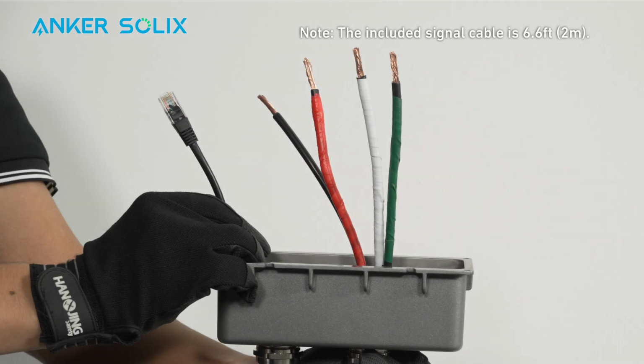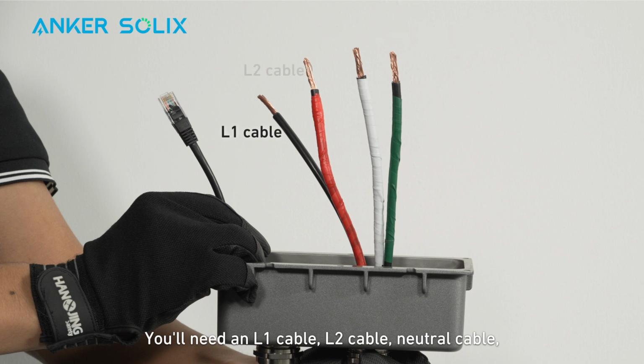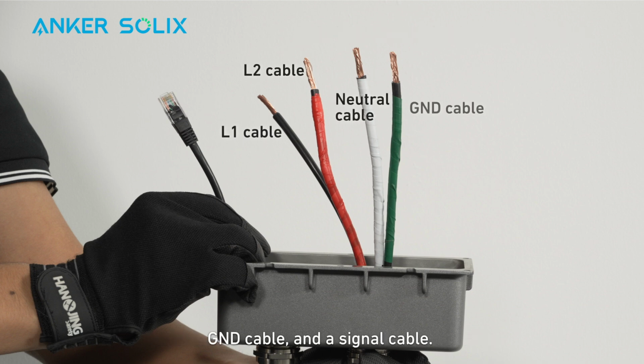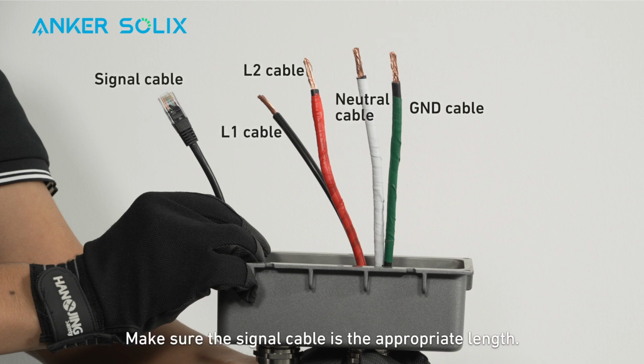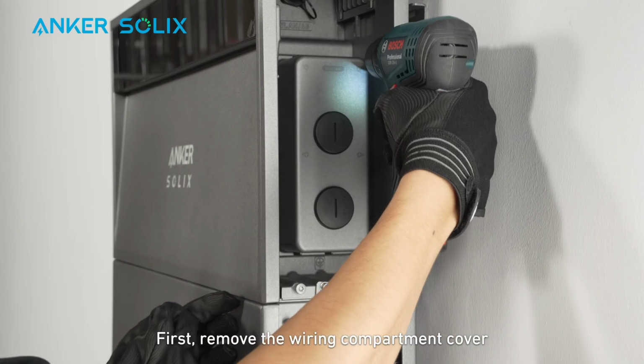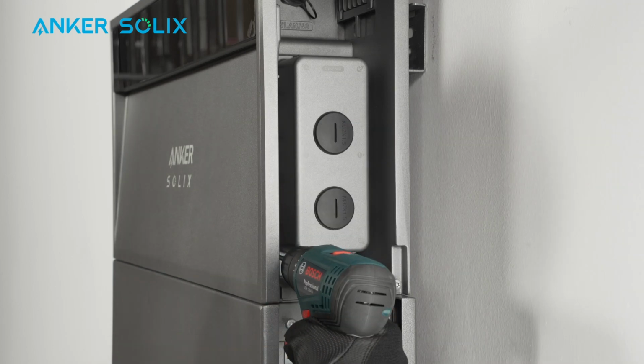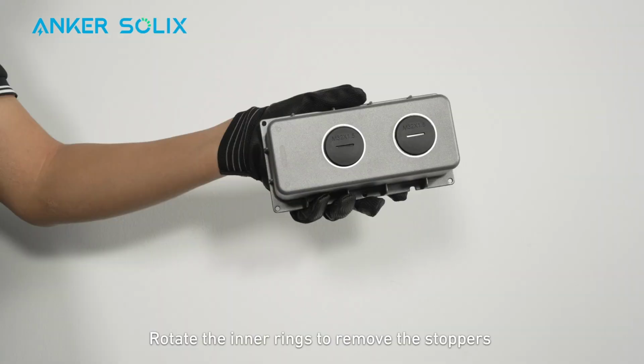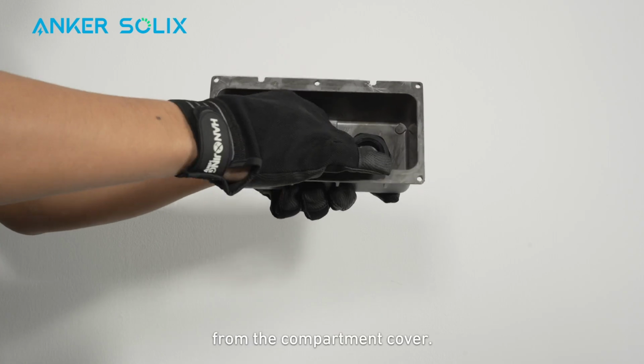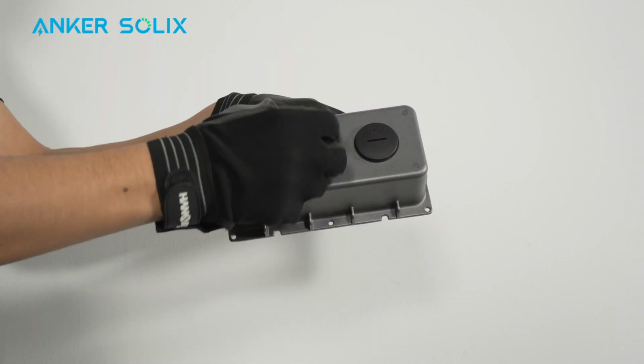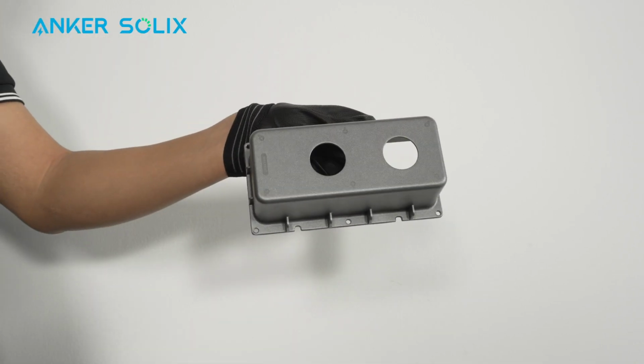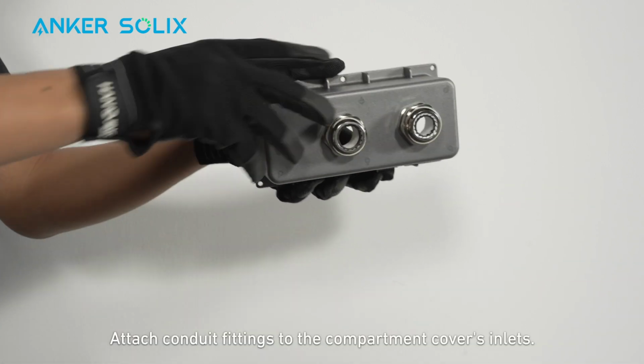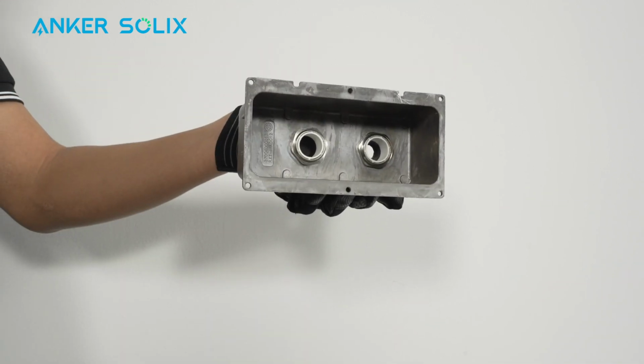You're ready to connect the power module to the backup controller. You'll need an L1 cable, L2 cable, neutral cable, ground cable, and a signal cable. Make sure the signal cable is the appropriate length. First, remove the wiring compartment cover from the right side of the power module. Rotate the inner rings to remove the stoppers from the compartment cover. Attach conduit fittings to the compartment cover's inlets.